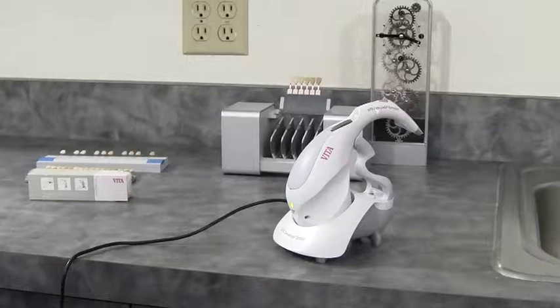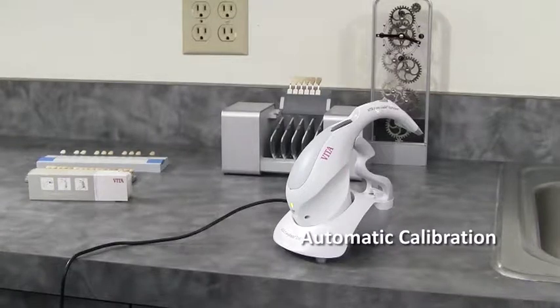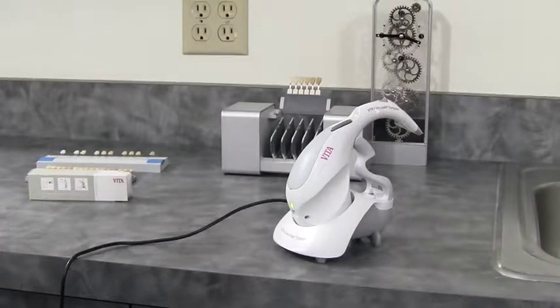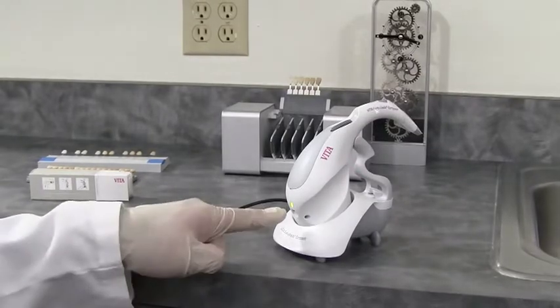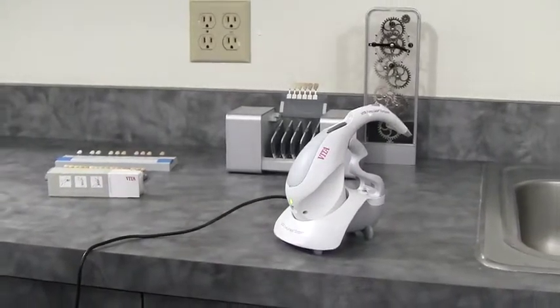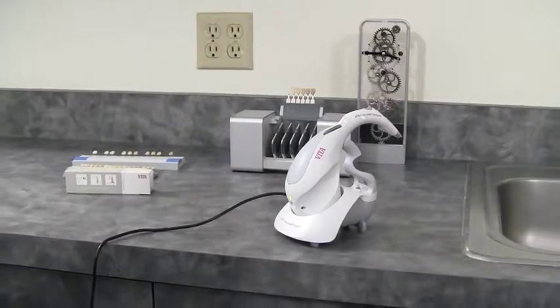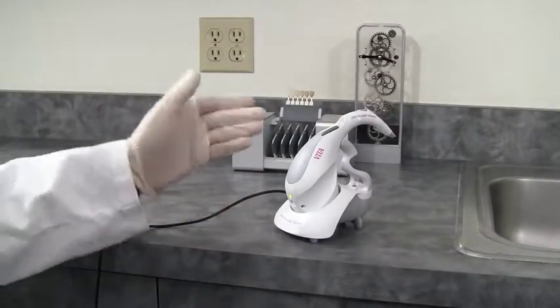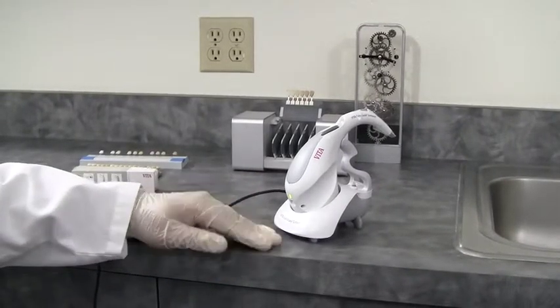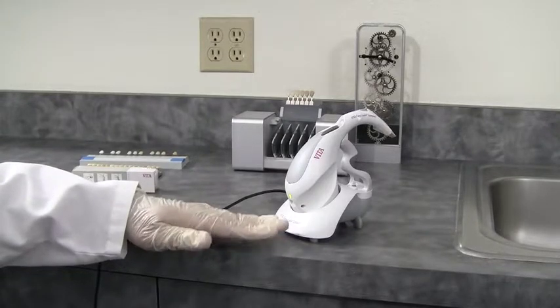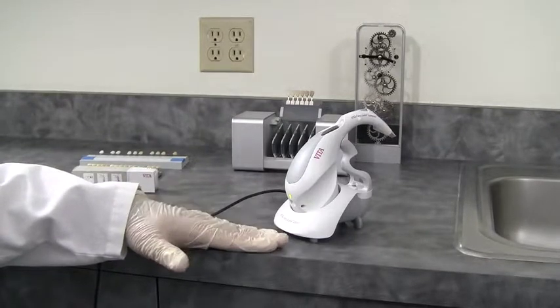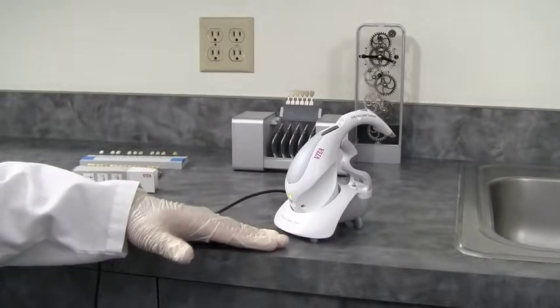I'm going to show you the automatic method of calibration. You'll notice that the unit is now powered. The power cable is going to the base unit and you can see the rear of the unit is illuminated, telling me it's charging. The unit, when you're first using it, should charge for 8 hours, and after that the nickel hydride battery has no memory. You can charge it anytime you like, or just simply leave it on charge.